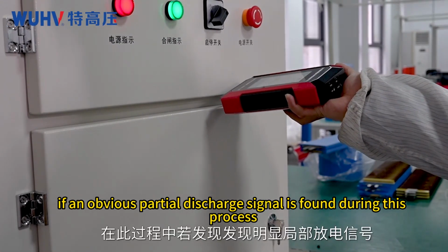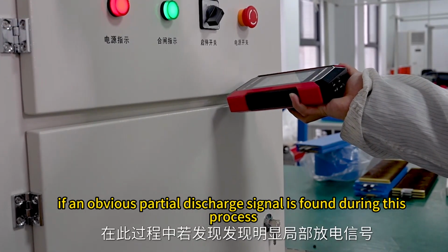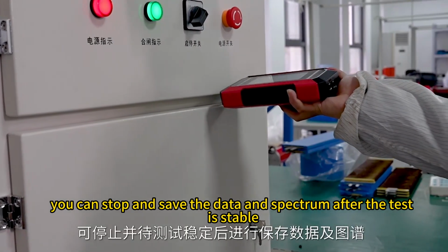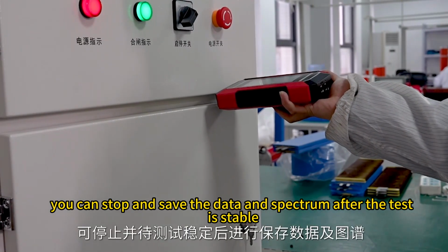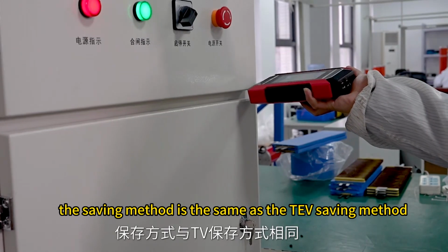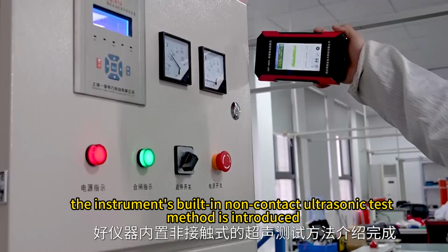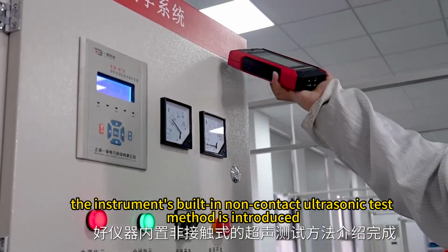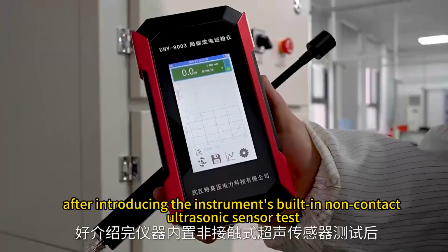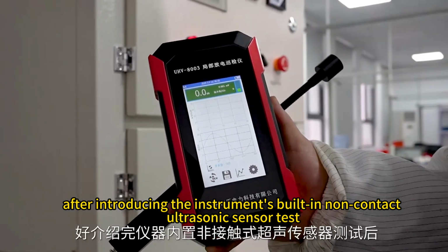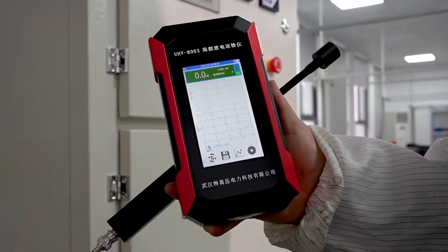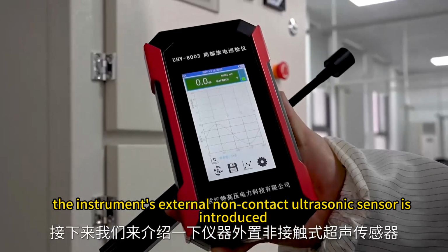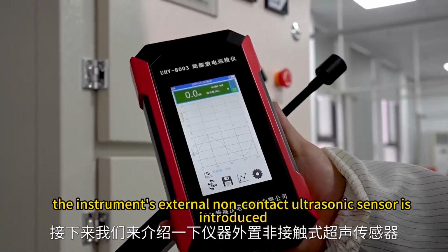If an obvious partial discharge signal is found during this process, you can stop and save the data and spectrum after the test is stable. The saving method is the same as the TEV saving method. The instrument's built-in non-contact ultrasonic test method is introduced. After introducing the instrument's built-in non-contact ultrasonic sensor test, the instrument's external non-contact ultrasonic sensor is introduced.